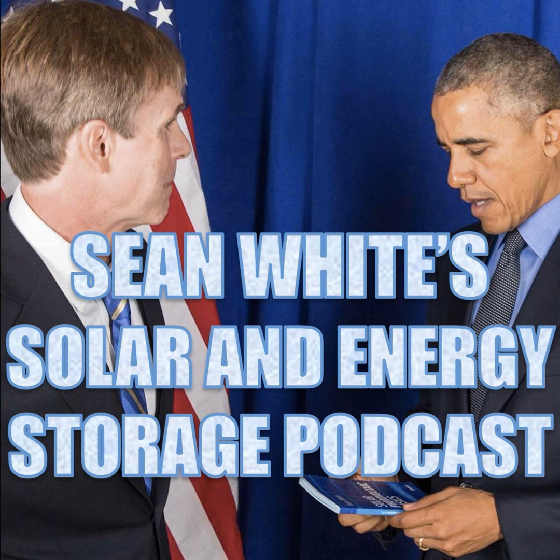So I want my refrigerator first, my lighting second, my communications, TV, those things. I want to make sure those things stay up and running, and I don't want to turn them off if somebody decides to run the dryer for some reason, forgetting that the power's out or something like that. That's where we're going to with all this load management. It's not a requirement in Article 705. In fact, we've added a bunch of load management information into Article 705 in the 2023 code. It's a design decision at that point.